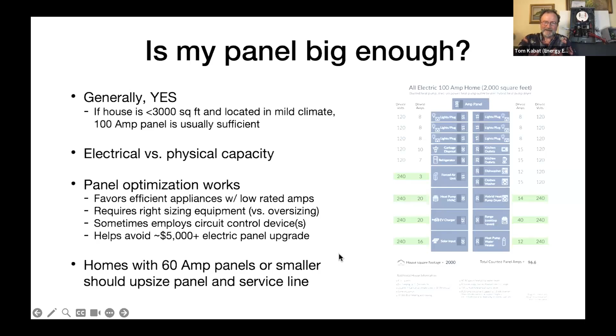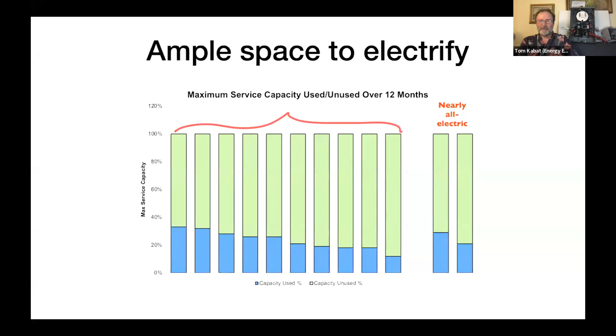This is a little bit of data from our San Mateo County study. The blue bars in the bottom are the percent of the panel utilization by the peak hour or 15 minutes of the whole year on that house. And the top of the green bar is the panel capacity. These to the left are the 10 homes in the study that were starting out as mixed fuel homes. And some of them had electric vehicles already. And then the two on the right are Josie's home and my home, where we're fully electric now and still down there. My house is fully electric and the peak is under 5 kilowatts. A 100 amp panel could give me 24 kilowatts, almost 5 times as much.